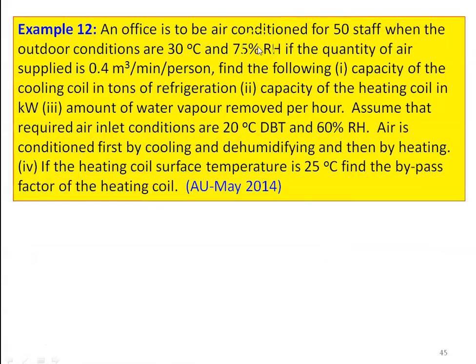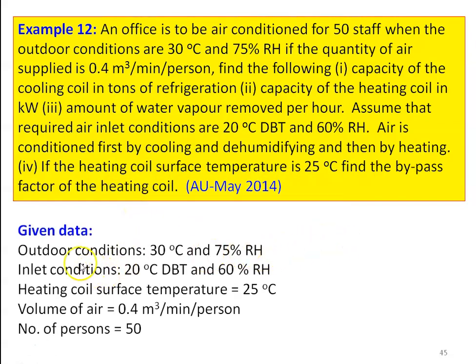An office is to be air conditioned for 50 persons when outdoor conditions are 30°C and 75% relative humidity. The quantity of air supplied is 0.4 m³/min per person. Find: capacity of the cooling coil in tons of refrigeration, capacity of the heating coil in kilowatts, and amount of water vapor removed per hour. Assume required inlet conditions are 20°C dry bulb temperature and 60% relative humidity. The heating coil surface temperature is 25°C.